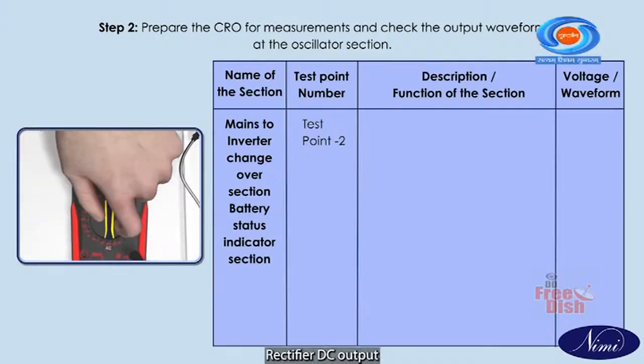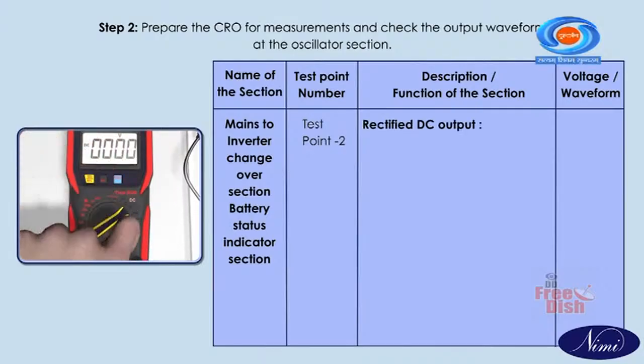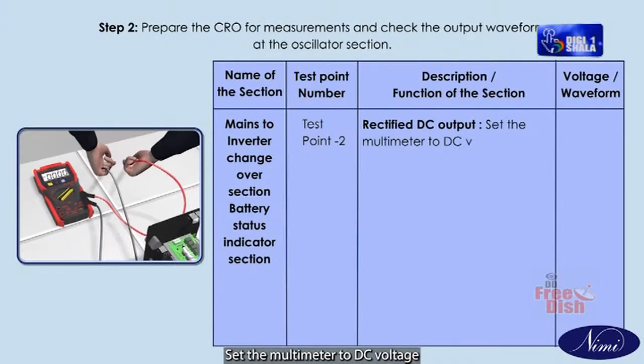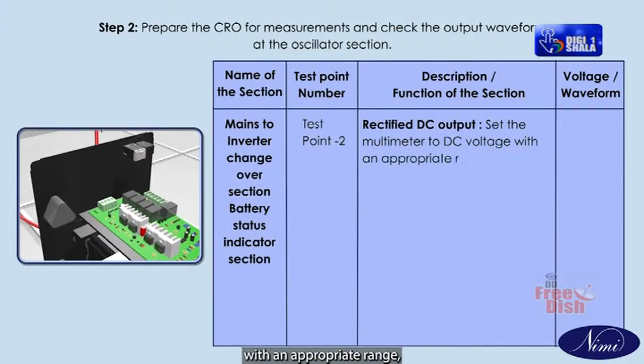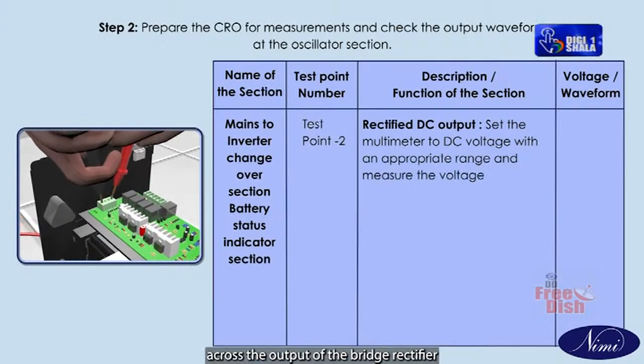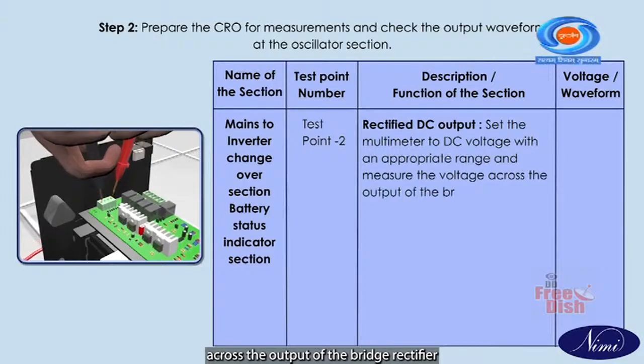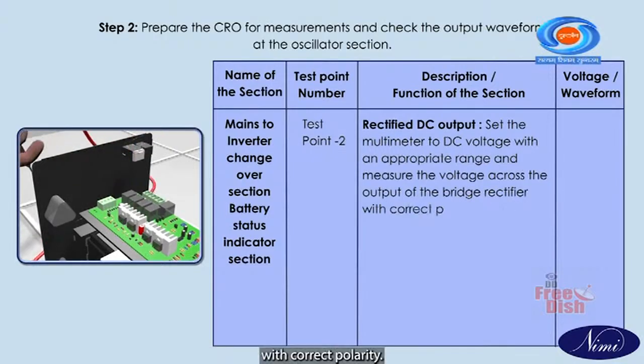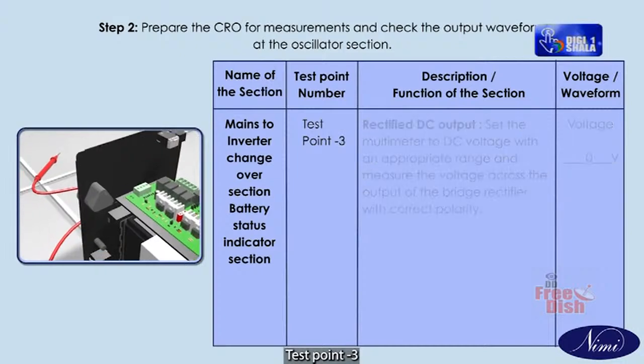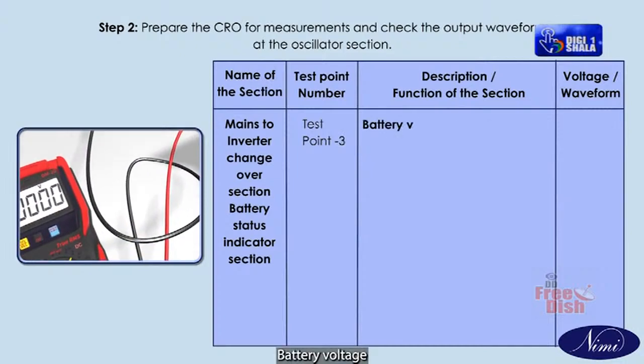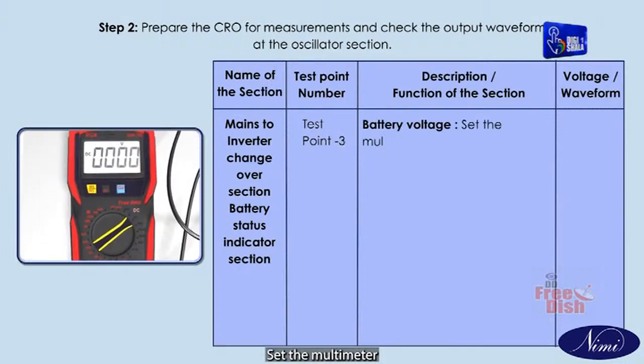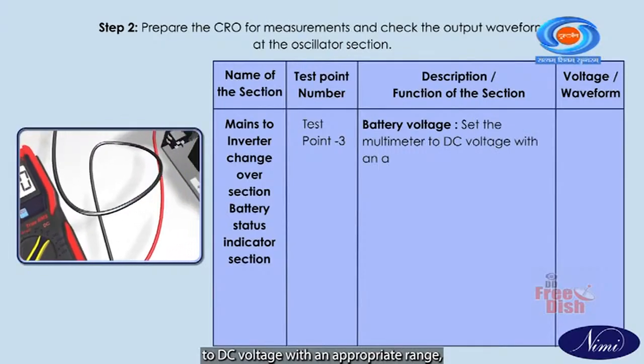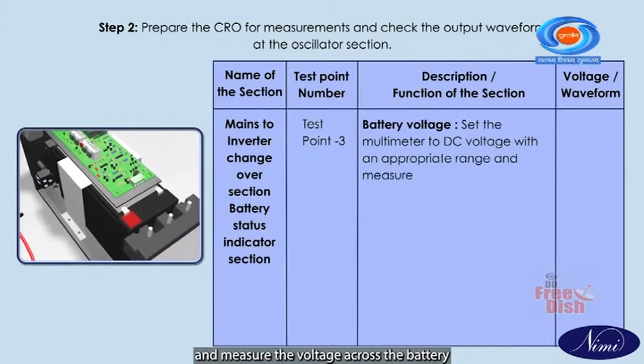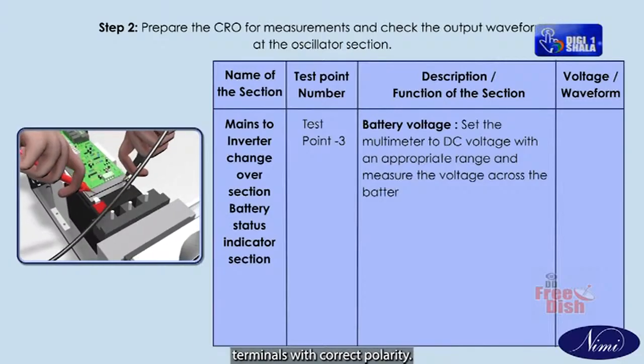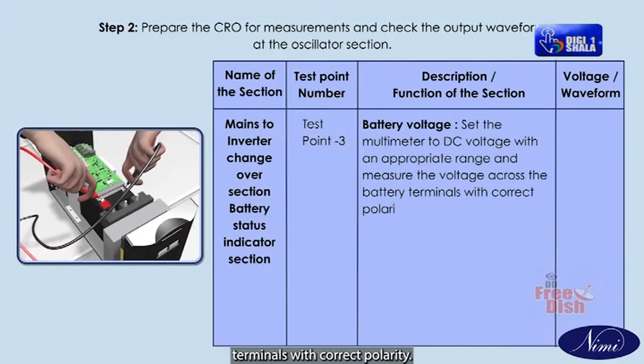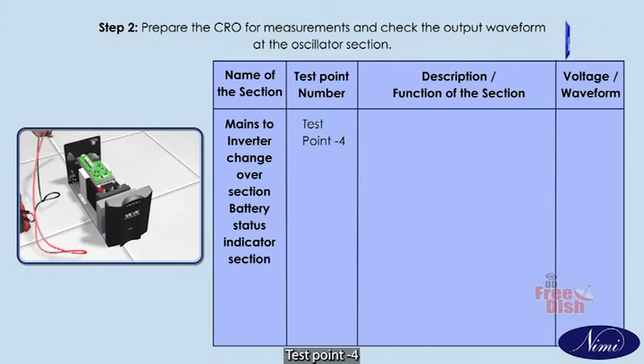Test point 2. Rectifier DC output. Set the multimeter to DC voltage with an appropriate range and measure the voltage across the output of the bridge rectifier with correct polarity. Test point 3. Battery voltage. Set the multimeter to DC voltage with an appropriate range and measure the voltage across the battery terminals with correct polarity.